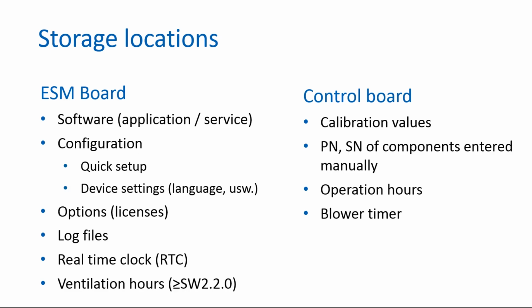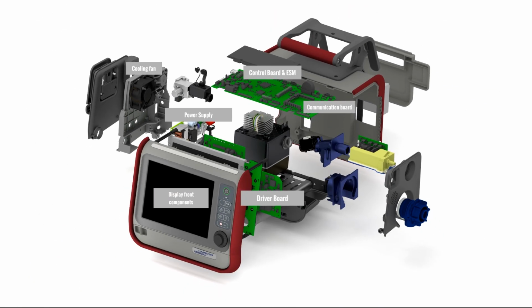The control board contains the calibration values, part, serial and revision number for the components which have no individual EPROM installed, the operation hours, and the blower timer. Next, we look at the driver board.